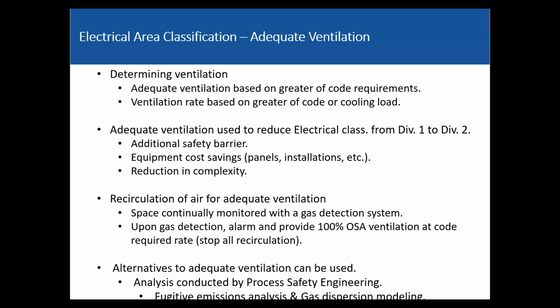reduction in complexity. So it's in everyone's best interest, and I would think with most modules we run into, you're going to have a reduction from Div 1 to Div 2. But the electrical guys, with their emergency lighting and egress, make it all Div 1. They have to pretend it's space. So you'll run into this. There will be some Div 1 equipment in a Div 2 space. All right.